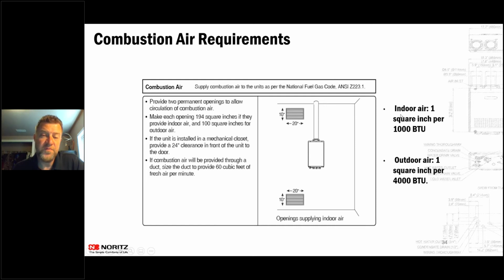If you're pulling it from inside air, you're going to need 1 square inch per 1,000 BTUs that you have there. So with these louvers, if you have a 10 by 20 and you're in the mechanical room and you're pulling combustion air from inside the house, you're going to need a 10 by 20 on the top, 10 by 20 on the bottom for that 199,000 BTU unit that's going to be in there. So these are all based off of the supplier combustion air in the National Fuel Gas Code. It could differ between the municipalities, but typically with combustion air, they follow those codes.